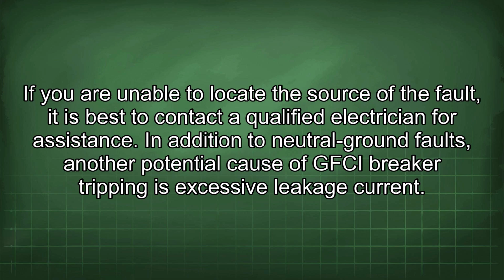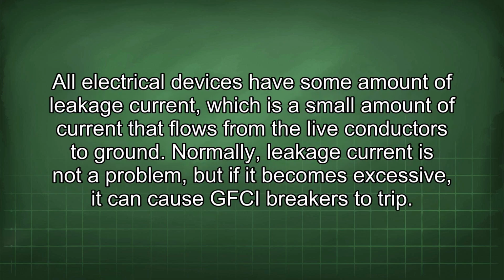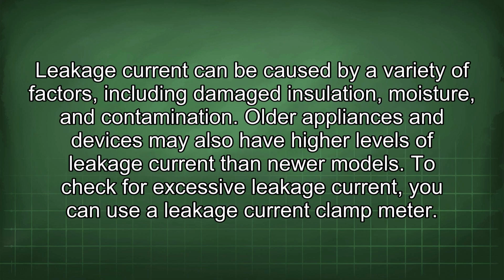In addition to neutral ground faults, another potential cause of GFCI breaker tripping is excessive leakage current. All electrical devices have some amount of leakage current, which is a small amount of current that flows from the live conductors to ground. Normally, leakage current is not a problem, but if it becomes excessive, it can cause GFCI breakers to trip. Leakage current can be caused by a variety of factors, including damaged insulation, moisture, and contamination. Older appliances and devices may also have higher levels of leakage current than newer models.